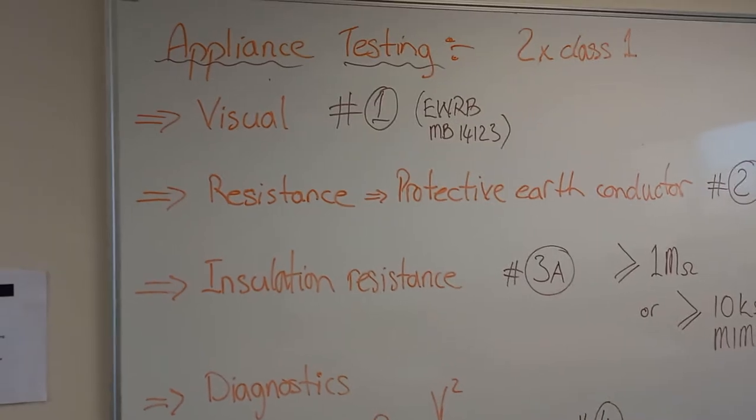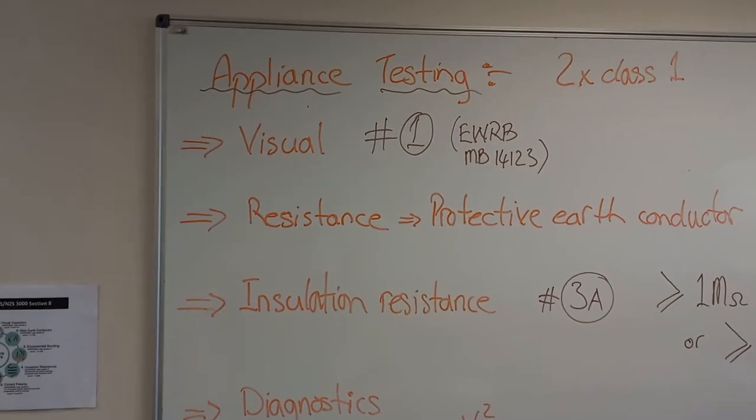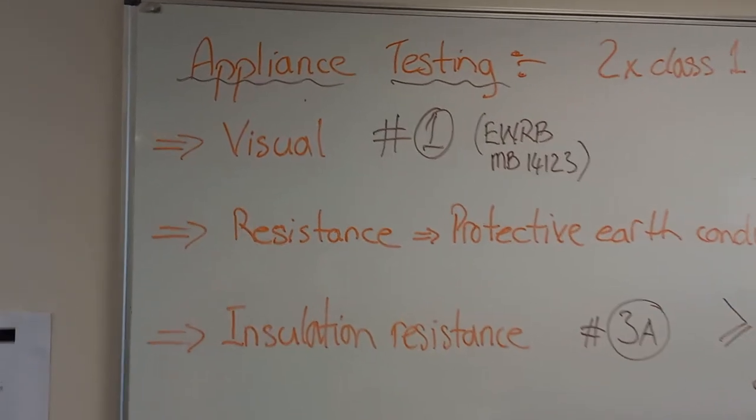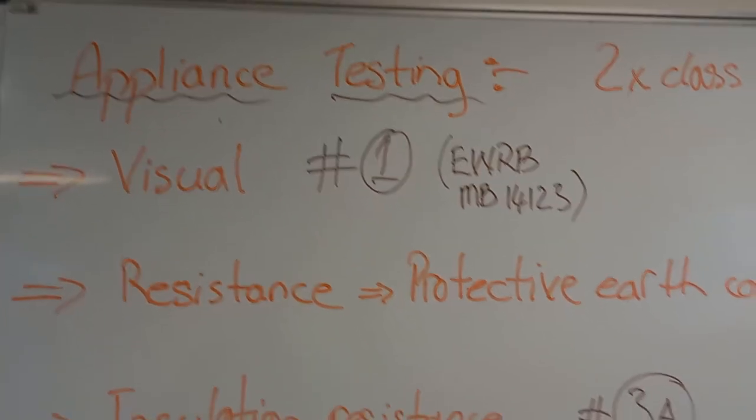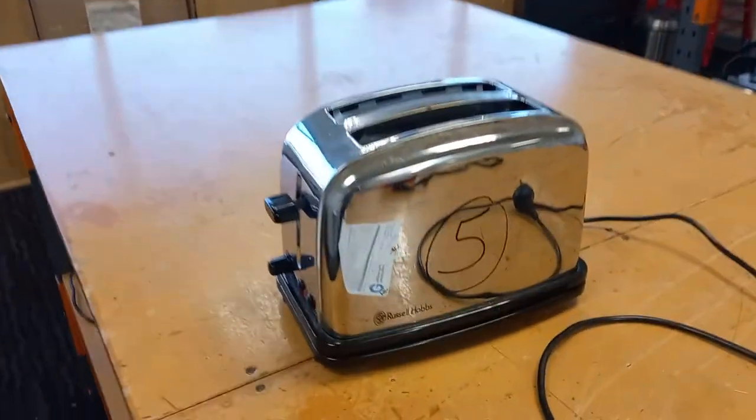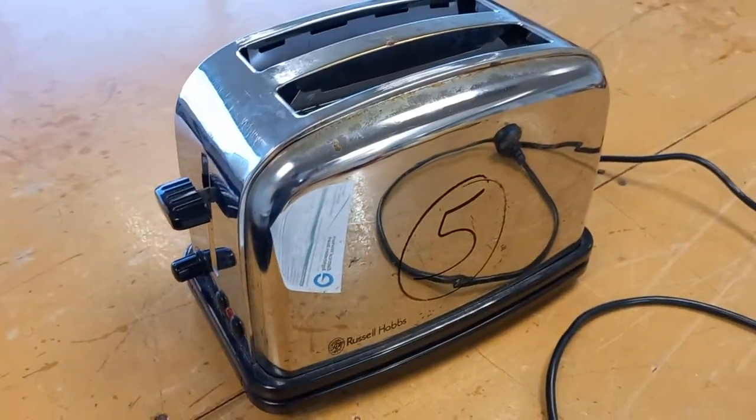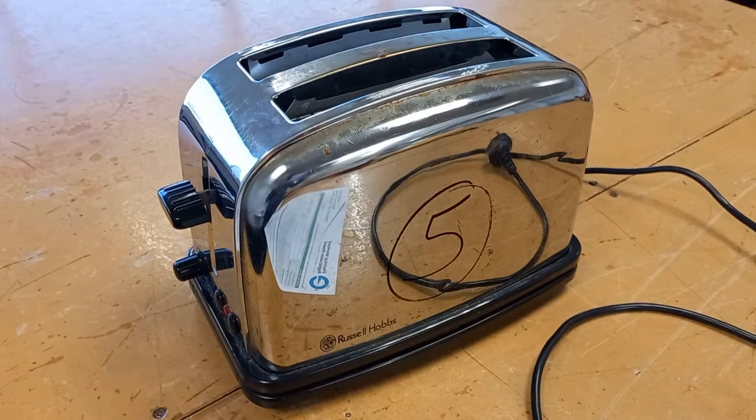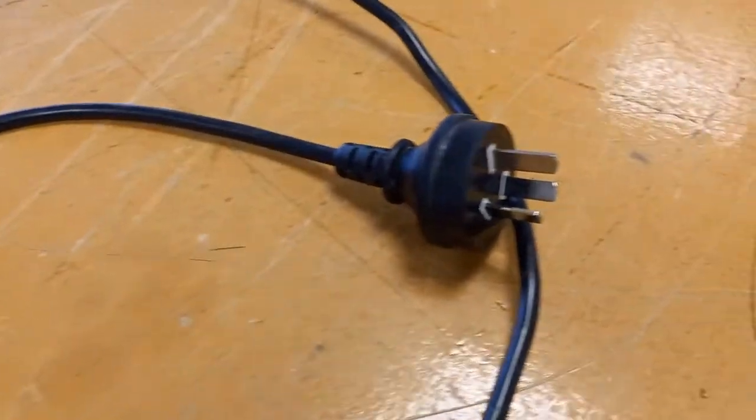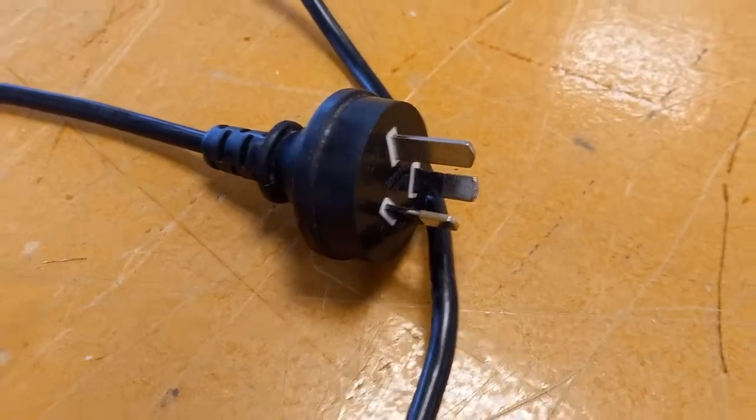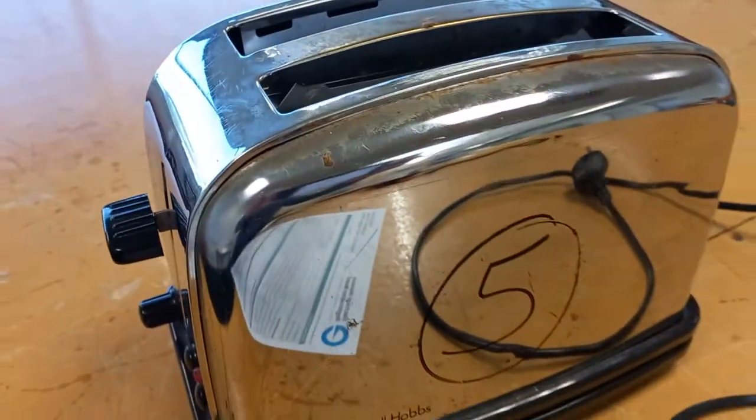The first test is the visual test, which is very important and doesn't use any instruments. Let's look at a typical Class 1 appliance - this pop-up toaster with a metal case. It is protected with a protective earth conductor from the earth pin on the plug to the case of the appliance.